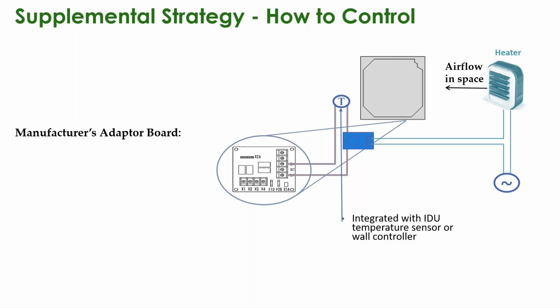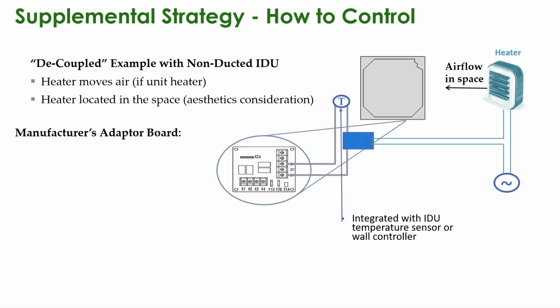Oftentimes you have high wall fan coils or ceiling cassettes, wall units. Everybody's got various different choices to meet the aesthetic or the space requirement, but not all of them can have an integrated heater added to them.